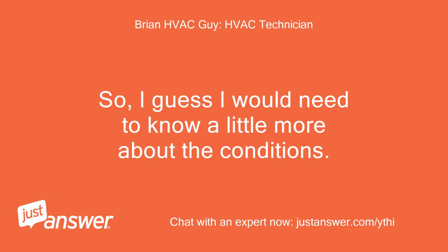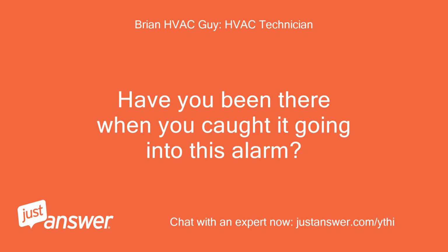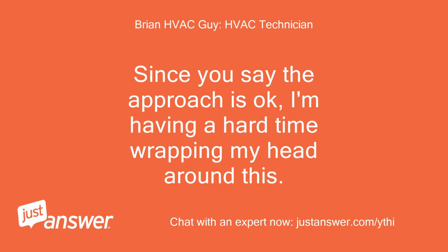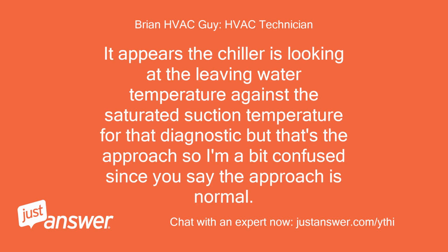So, I guess I would need to know a little more about the conditions. Have you been there when you caught it going into this alarm? Since you say the approach is okay, I'm having a hard time wrapping my head around this. It appears the chiller is looking at the leaving water temperature against the saturated suction temperature for that diagnostic, but that's the approach, so I'm a bit confused since you say the approach is normal.